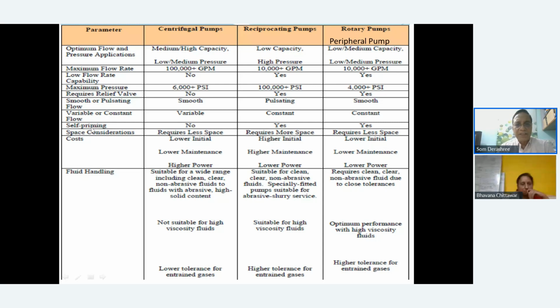Then self-priming: centrifugal is no. Yes, the reciprocating pumps are self-priming because they are pushing the liquid forward and backward. On space constraints, the centrifugal requires less space, and the reciprocating requires more space comparatively. Cost wise, yes, the centrifugal is low cost, and the reciprocating is of course a very costly affair. That's why you find that it's getting phased out in most applications. Unless it is a very viscous and thick fluid, people normally go for the centrifugal pump, and all kinds of fluid are being handled there.